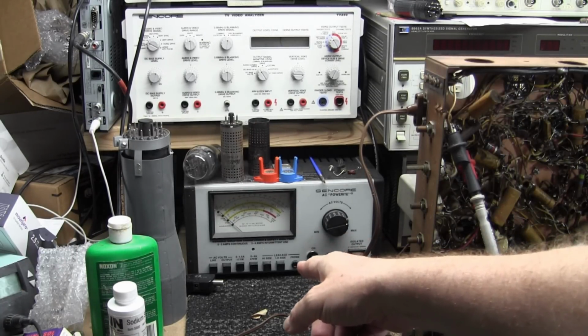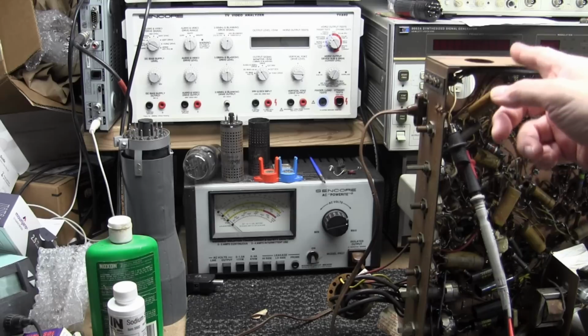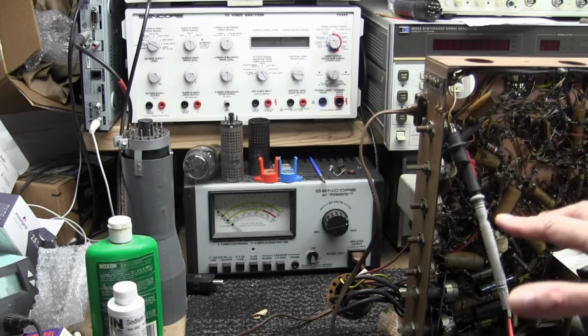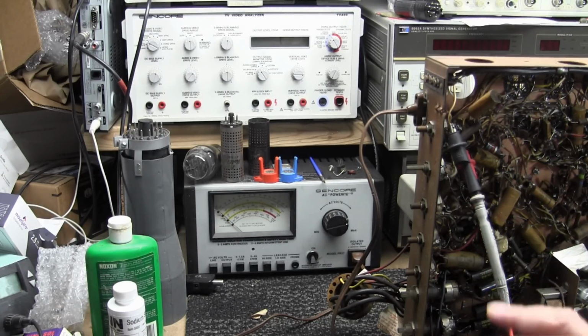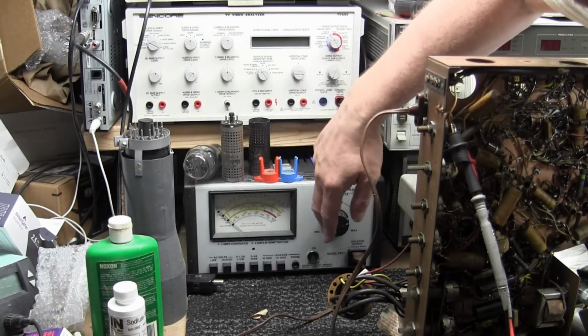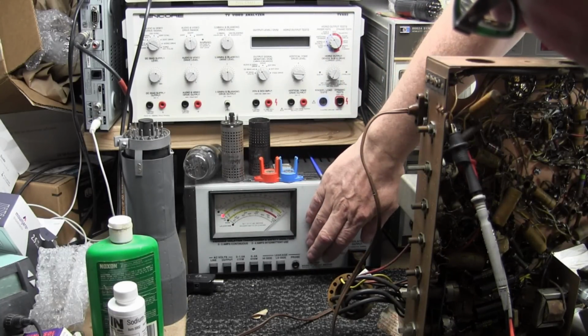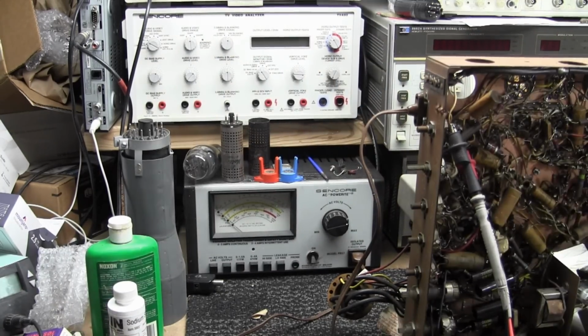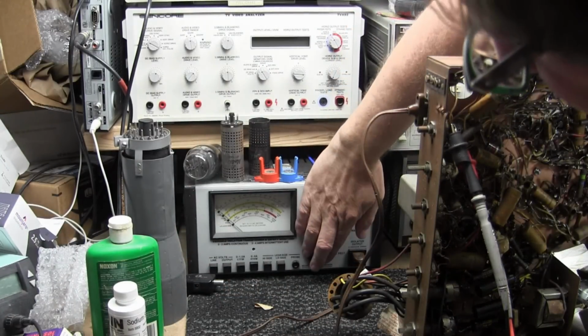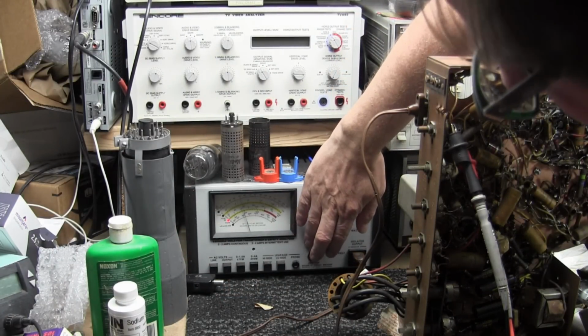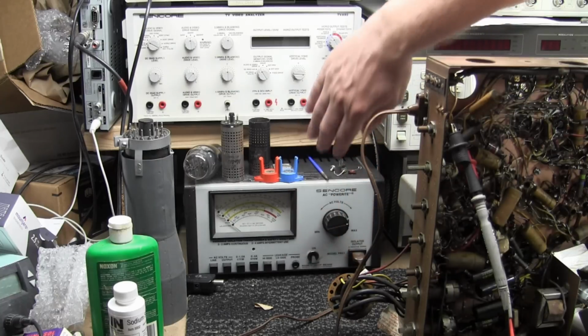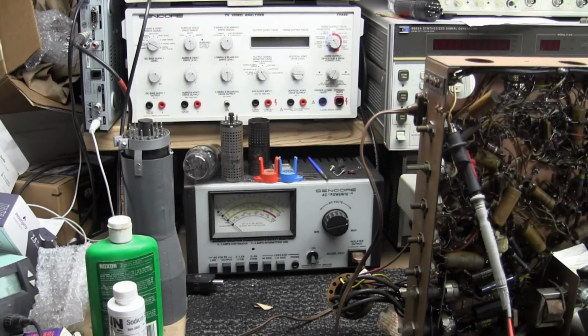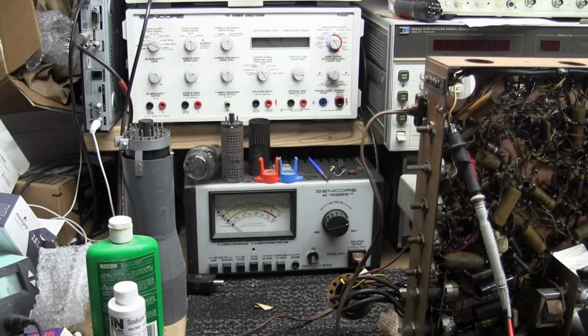Alright, so what I was looking at was the meter on this. I have it on the 1.5 amp scale. I know this set draws about an amp, just slightly over an amp or so when it's running properly. So when I turn this on, it pegged the meter. I'll show you that again. So that's not good. If I put it on a 4 amp scale, so it'd be 4 amps full scale, it's not getting there. We're under 2 amps total, so it's just off the scale on the 1.5 amp scale. So we're kind of dead short.